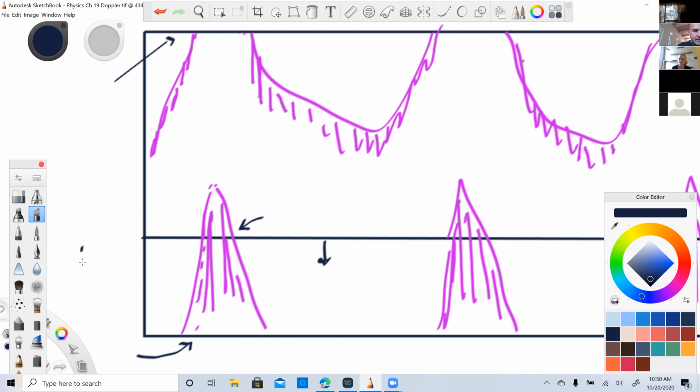So we change our PRF. We take our little PRF button, and we're going to decrease it. Pulse repetition frequency. What does it even mean to change the pulse rep? Like why? It's a sampling rate. We always have a sampling rate with pulsed ultrasound, whether it's grayscale or pulse wave like this. There's always a sampling rate.